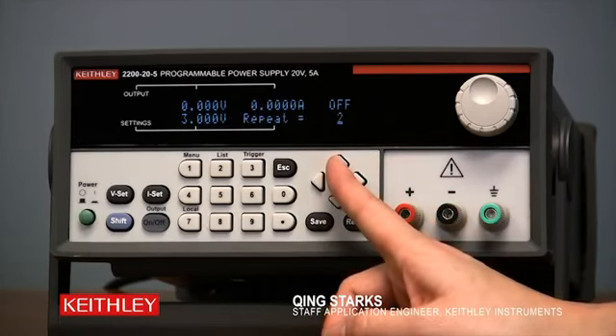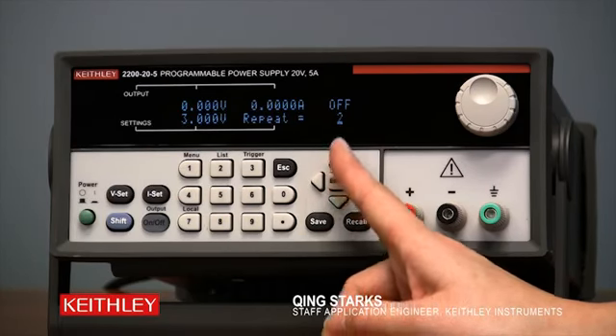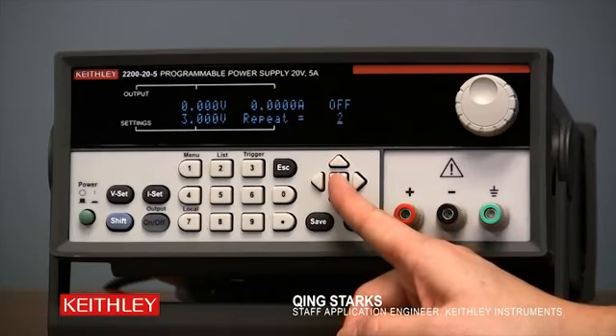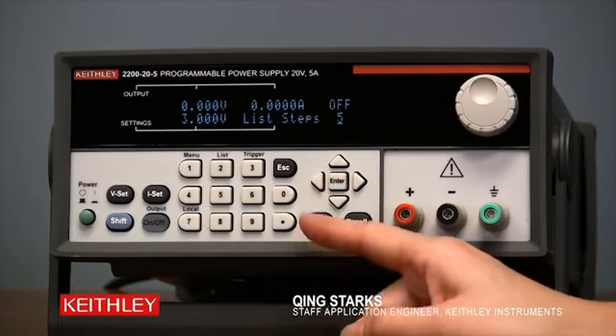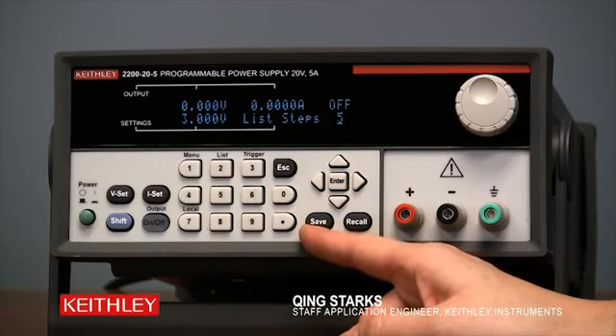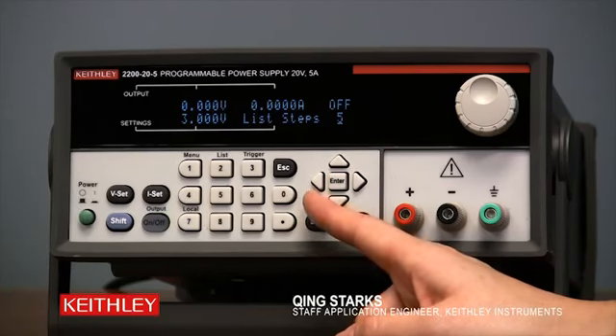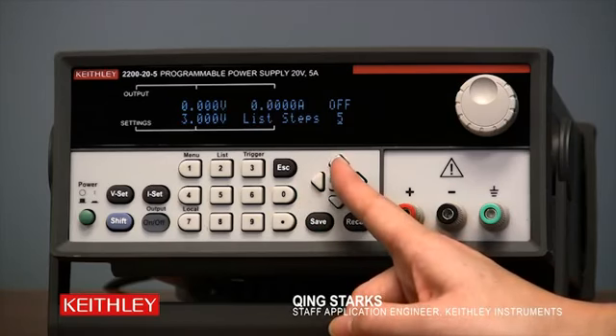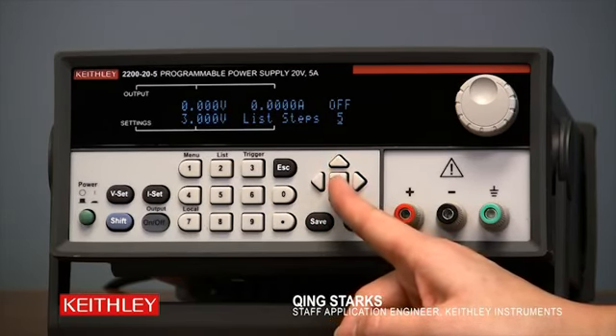Next, the display will prompt you to enter the number of repetitions of this particular list. For this demo, we're repeating the list twice. So 2 and press Enter. The next step is to configure the number of steps in the list. Since we said this is a 5 voltage points, the number of steps is 5. The display is showing 5 already. We'll just press Enter.